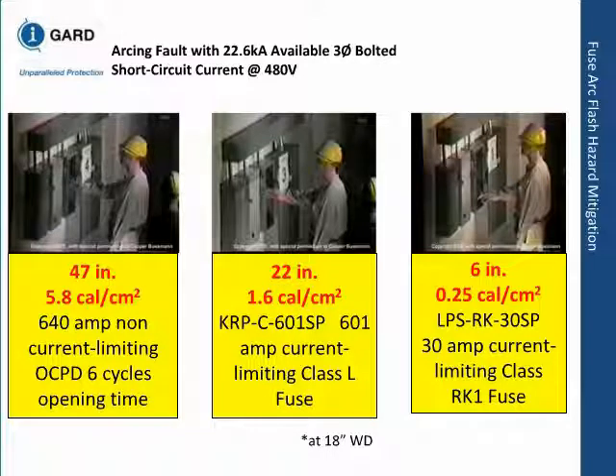Now, the last column you see, you have a 30 amp fuse. On 26 kA, it goes into current limiting very well. So you have a 6-inch arc flash boundary and only 0.25 calories per centimeter squared hazard. What is the arc flash boundary? Where the incident energy is going to be 1.2 calories per centimeter squared or higher. That is the energy the medical field tells us can cause onset of a second-degree burn.